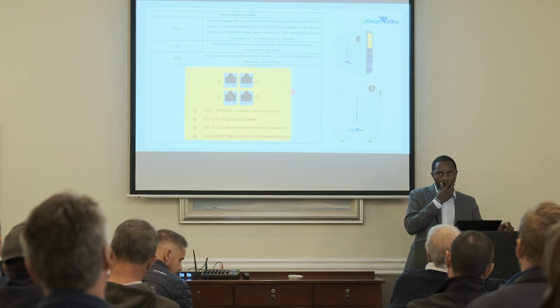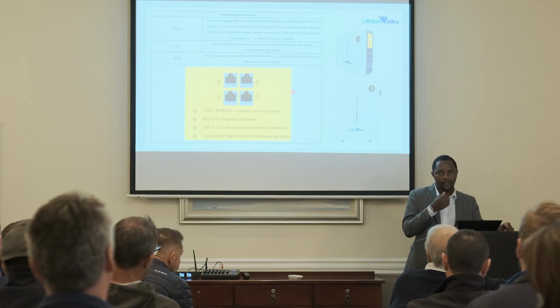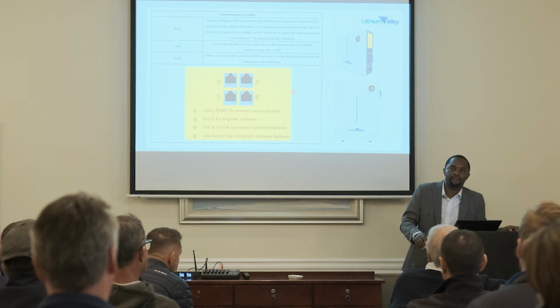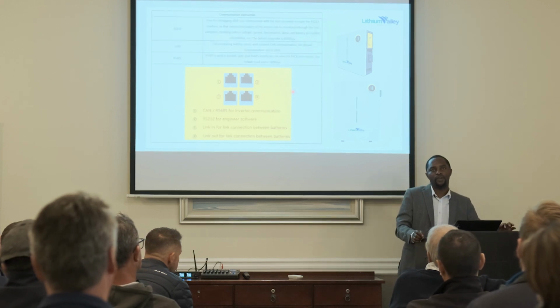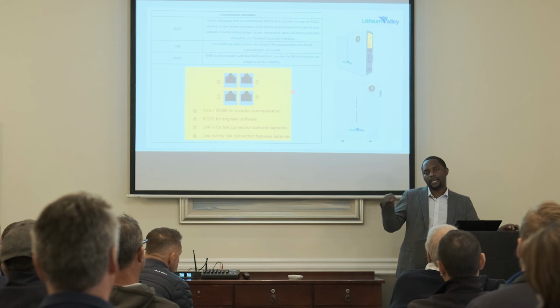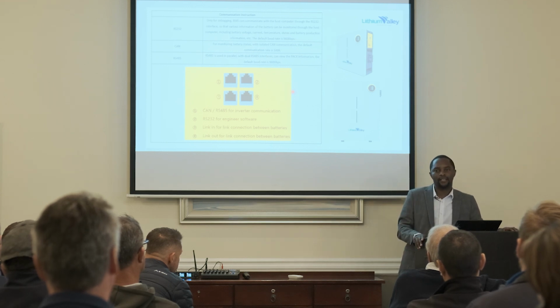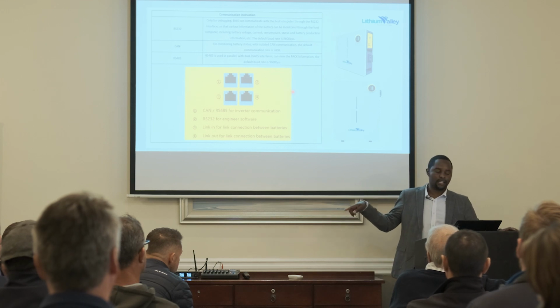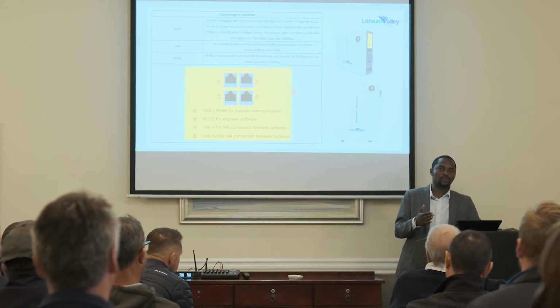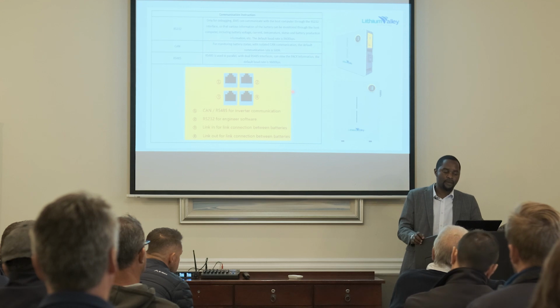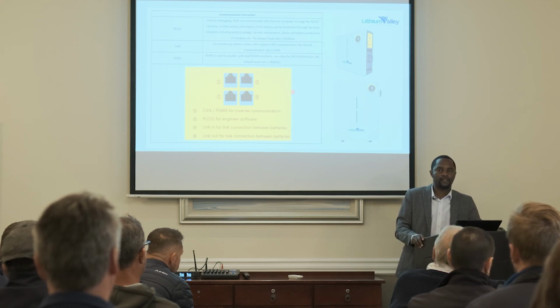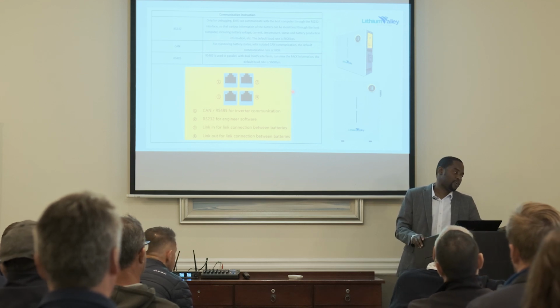Your communications cable is standard RJ45. Yes, they are standard RJ45 and they are actually provided. Then the communication between battery and battery is RS-485. Then from your master battery pack to inverter, it's CAN bus. So this is standard, but it uses RS-485 protocol. Then the CAN is only from your battery number 1 to the inverter. Then it's provided for in each package.